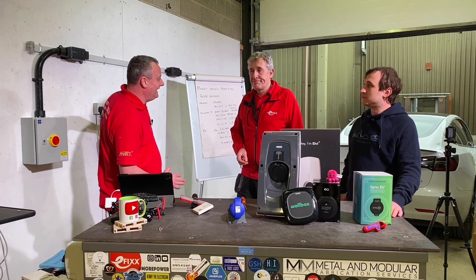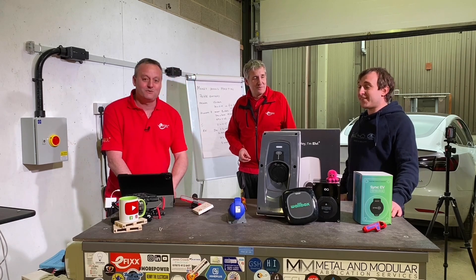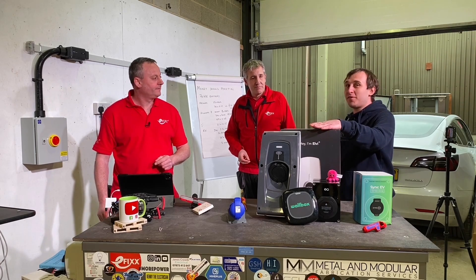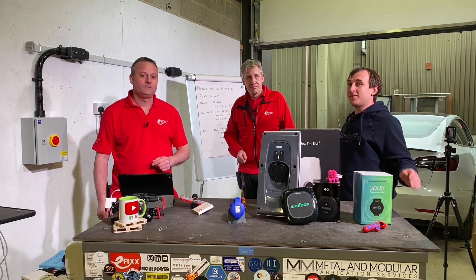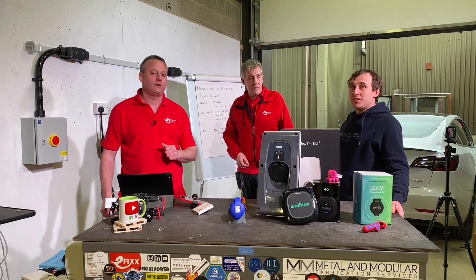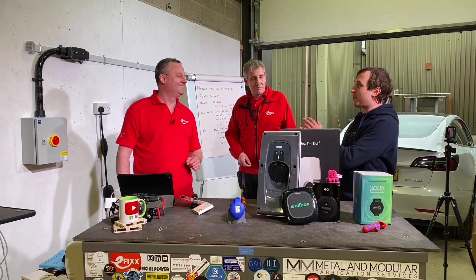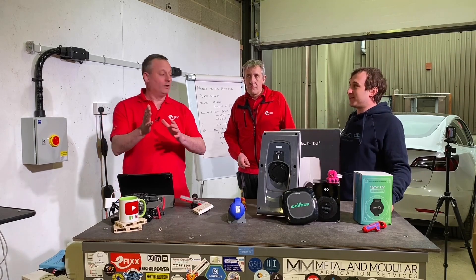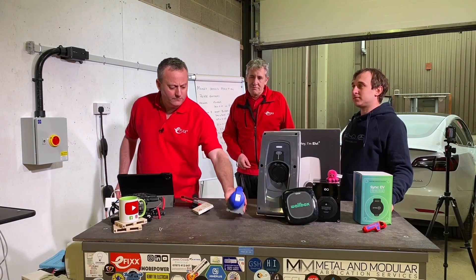The simple socket outlet on your wall can be solved with one of these dedicated EV chargers, because they have a lot of the protections built in - especially PEN fault detection - and many now also have DC leakage protection built into the unit itself. So when an electrician says you need to fit one of these, there are a lot of good reasons why they should. If you ring an electrician and ask for an outside socket for your electric vehicle, I'd hope he wouldn't simply fit a weatherproof 13-amp variety.